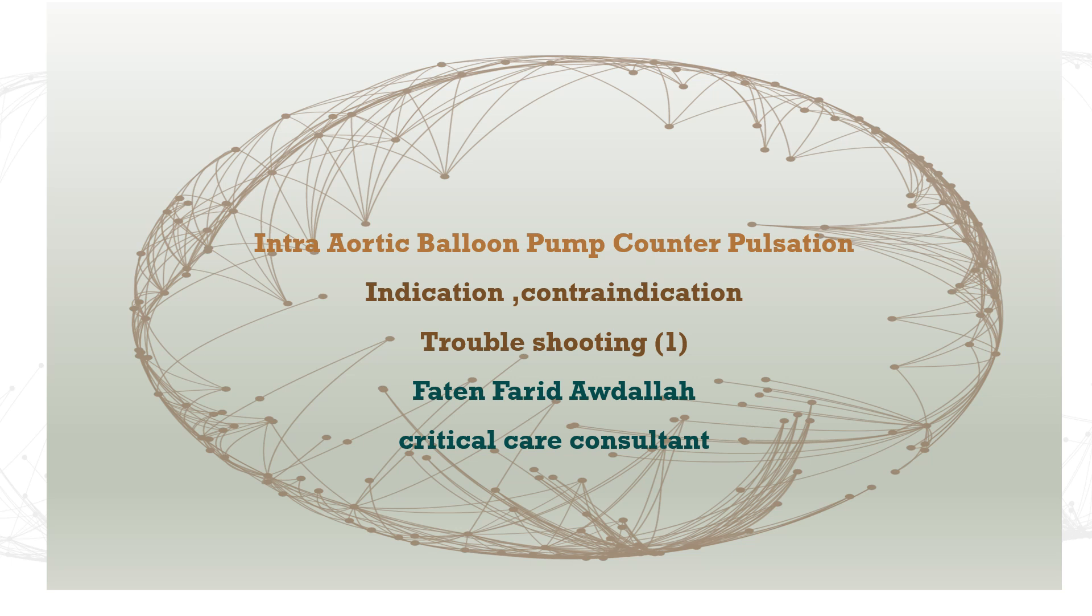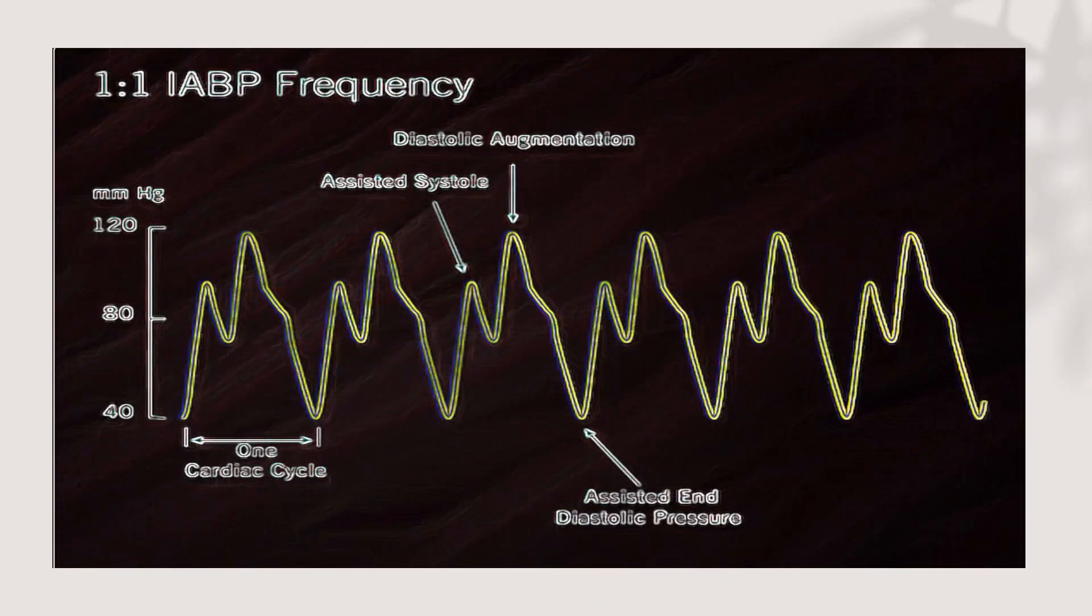In the previous lecture, we explained the problem related to timing error and how to diagnose. Today, we will try to solve this issue and see its effect on hemodynamics. Just a reminder, for this picture of intra-aortic balloon pump at one-to-one frequency fully assisted, we can't assess the timing or the problem in inflation or deflation. We need to go to one-to-two.